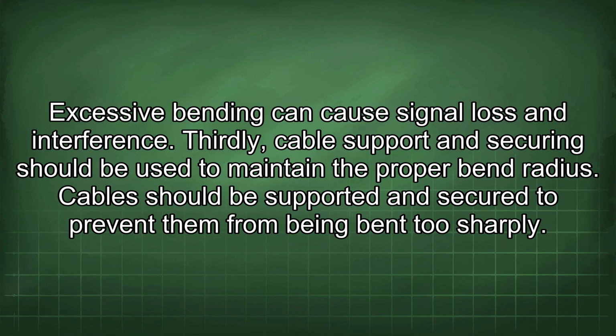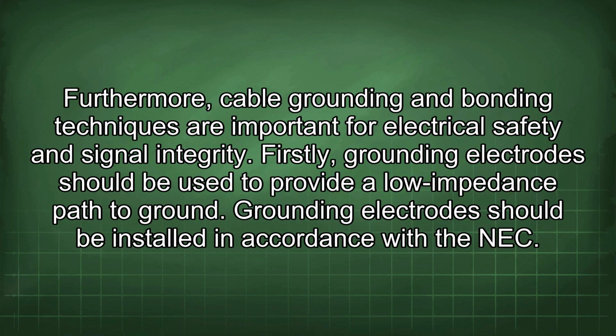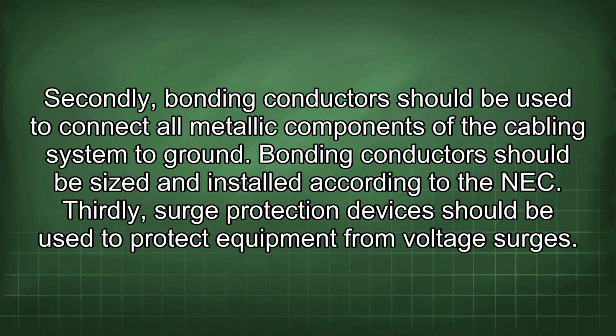Thirdly, cable support and securing should be used to maintain the proper bend radius. Cables should be supported and secured to prevent them from being bent too sharply. Furthermore, cable grounding and bonding techniques are important for electrical safety and signal integrity. Firstly, grounding electrodes should be used to provide a low impedance path to ground. Grounding electrodes should be installed in accordance with the NEC. Secondly, bonding conductors should be used to connect all metallic components of the cabling system to ground.